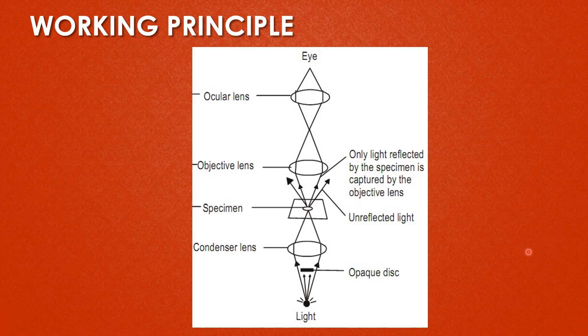This is the working principle of the dark field microscope. The opaque disc blocks the light coming from the light source, preventing it from entering the objective lens directly. Only light that is reflected off the specimen enters the objective lens, and it reaches the eyes through the ocular lens or eyepiece. Because there is no direct background light, the specimen appears bright against a black background — this is why it is called the dark field.